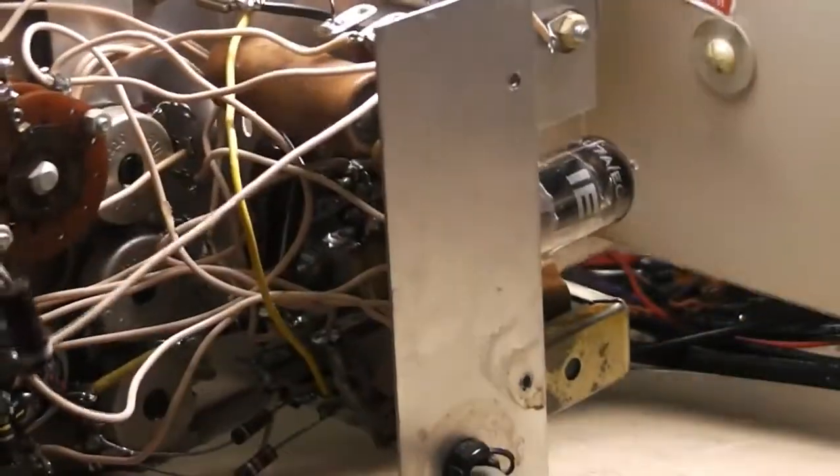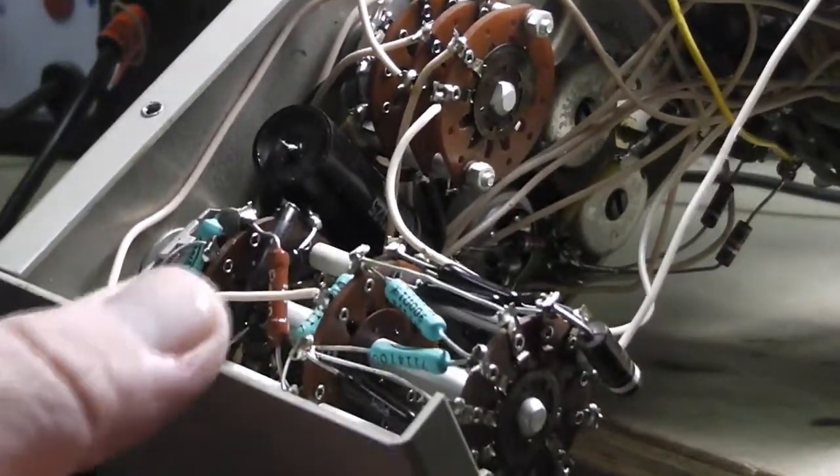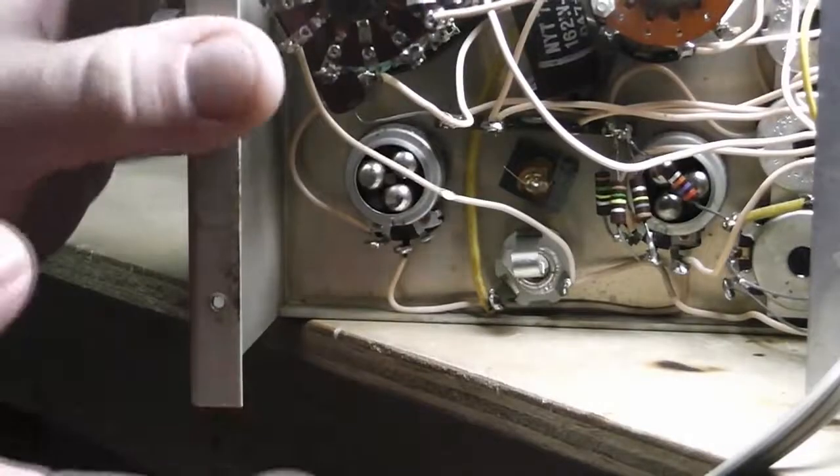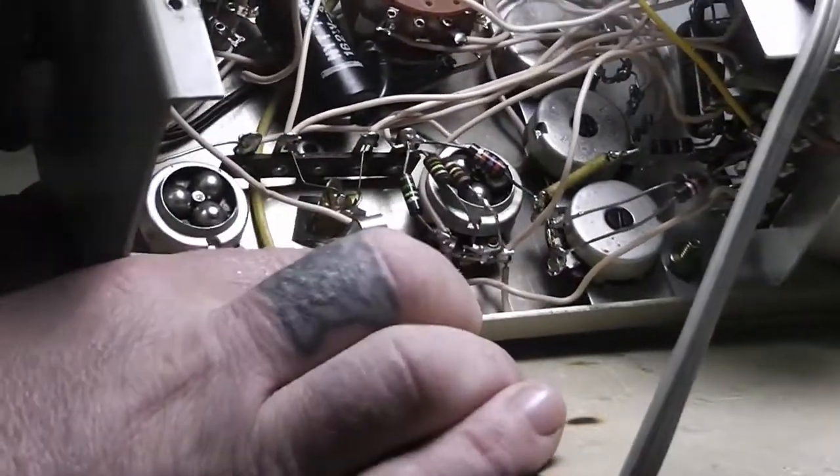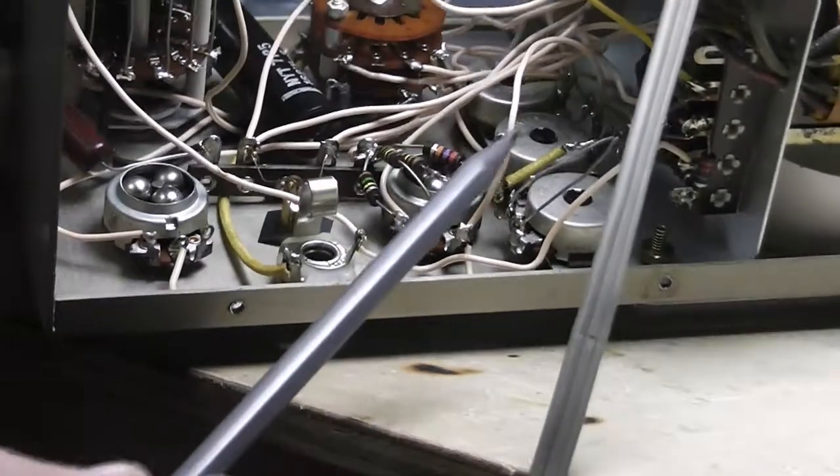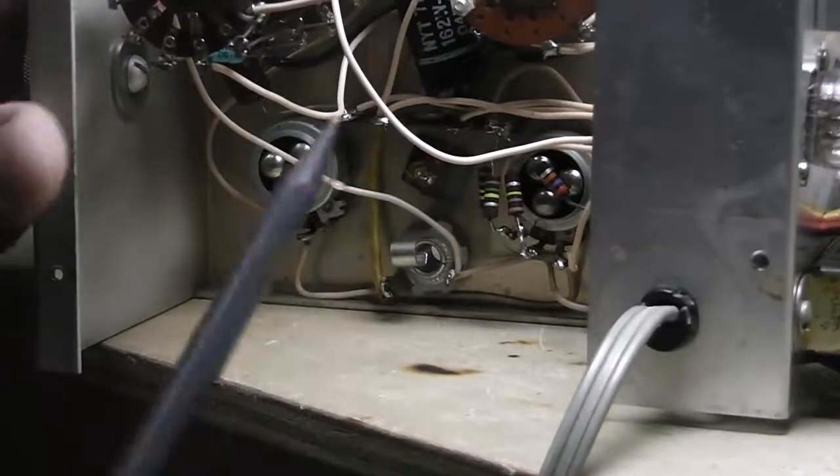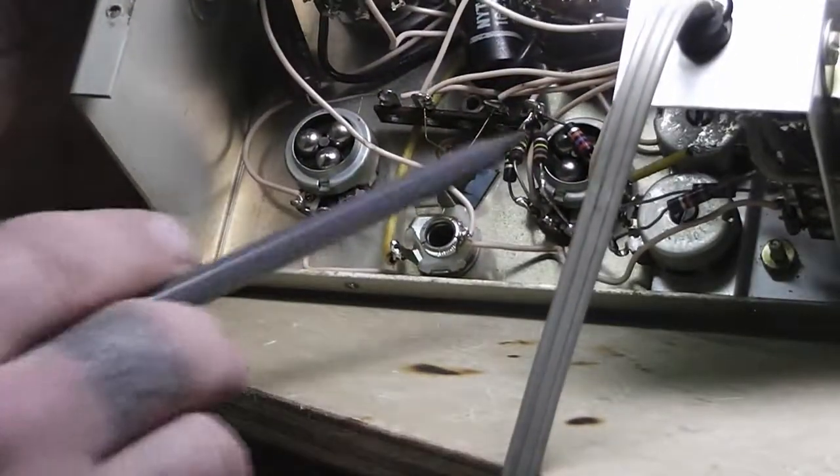There's two capacitors here, one down here, and a capacitor here. These are disk type, they hardly ever fail so I'm not worried about those. I'll leave those in there. The resistors of course, we won't be changing any of those unless they've just completely failed for some reason. These are all purposely set and designed so the meter accuracy is right, and they're usually very high precision resistors anyway, but we'll check the rest of them.